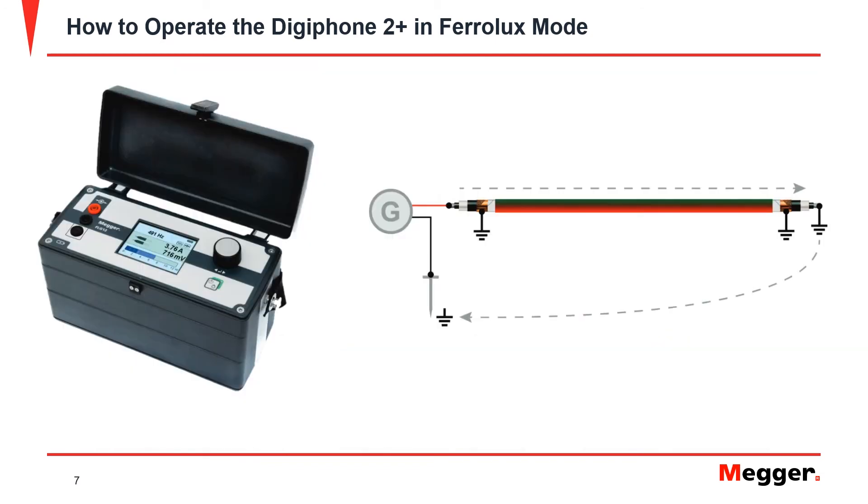When using the IFS on de-energized cables, ensure that all applicable safety requirements have been followed and that the cable is grounded on the end opposite the signal generator. If the cable has a shield or a switch, then connect the red output lead from the generator to the center conductor of the cable. Connect the black output lead from the generator to the ground spike, which should be driven close to the generator.